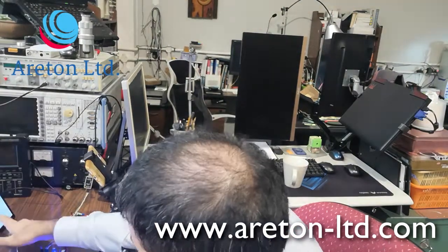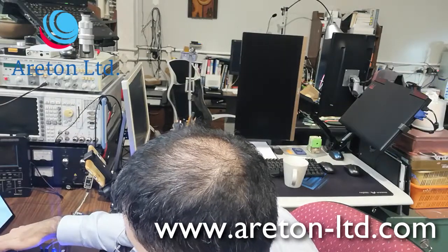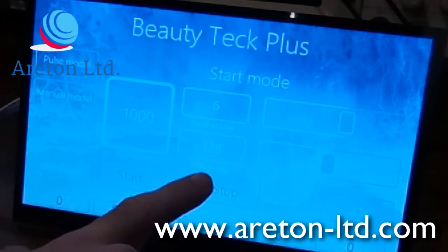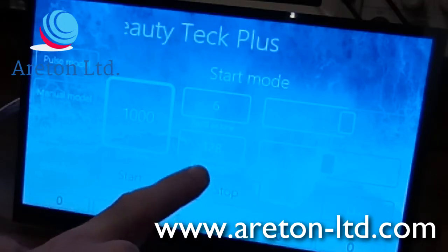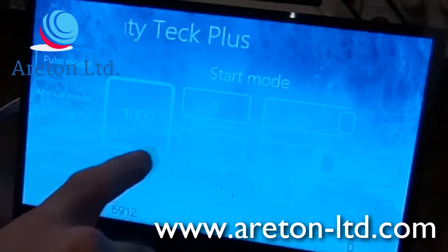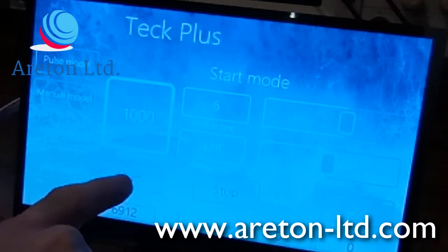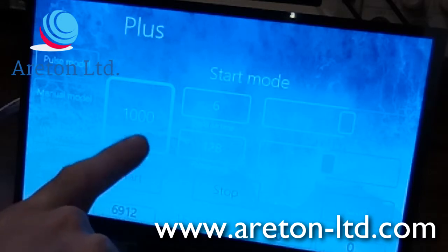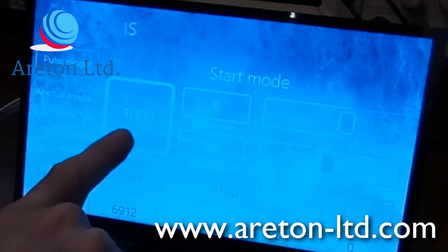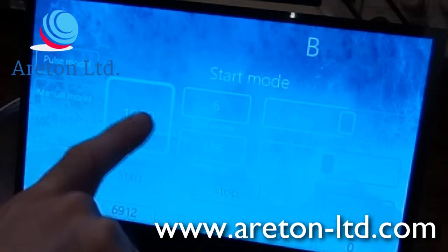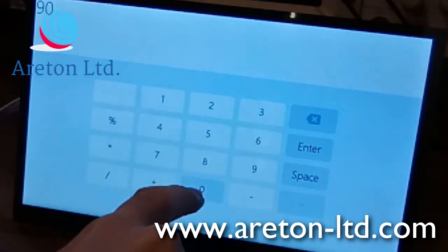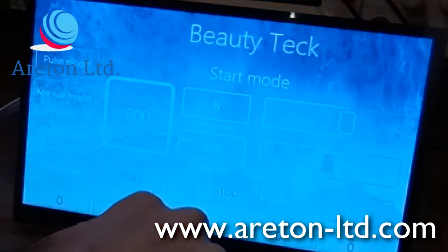So what I'm going to do is go into the start mode first. I've got to set it up so that the start time is 1000 milliseconds. So basically it's going to keep the arc on for 1000 milliseconds. Because we actually talked about 900 milliseconds in the video, we're going to do 900 just to make it an exact match.